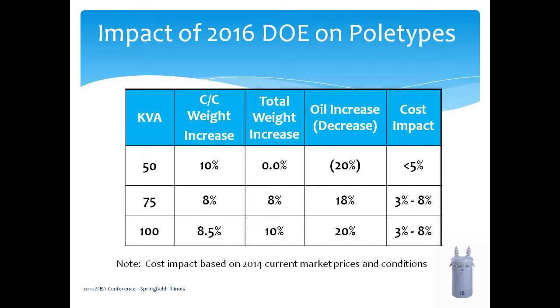But you can see the major increase in the 50s was the core coil assembly weight. We actually went down on oil, and you'll see the cost impact was very insignificant. So you can see there's some things that make a little sense, because when you run more efficiently, you can put more core steel in it. You can actually try to decrease the size of the tank, you won't need as much oil in it, so without as much oil in it, it drops the weight.